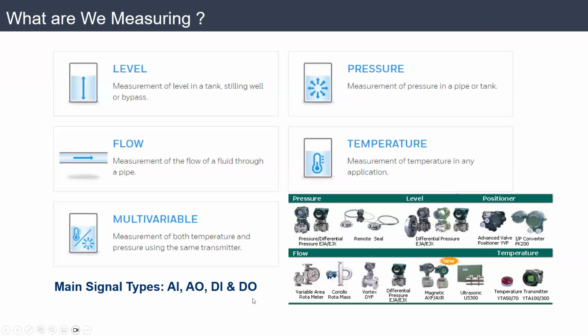So we have 4 types of signals that transfer from the plant to the control room. We'll start the journey from the transmitters or pumps, for example, to the control room. If the signal transfers from plant to control room, we call it input. If the signal transfers from the control room to the plant, we call it output. If the signal is numbers or percentage, we call it analog. If the signal is a pulse or on-off or normal/alarm, for example, we call it digital. I hope it's clear by now - we will have more examples on this.